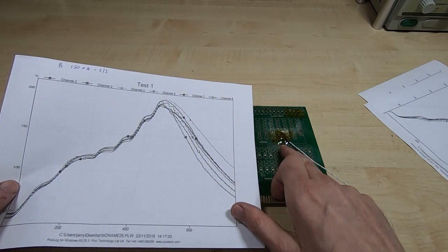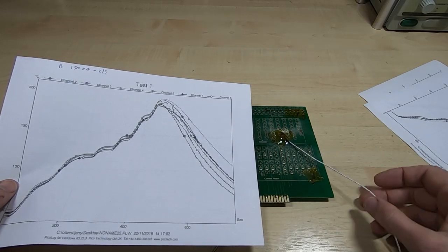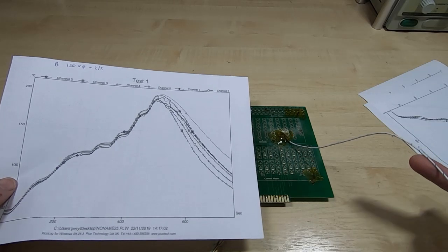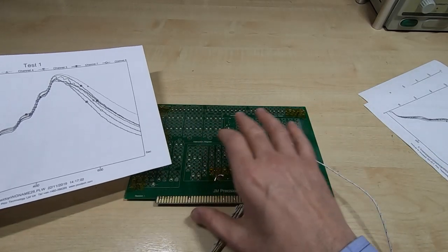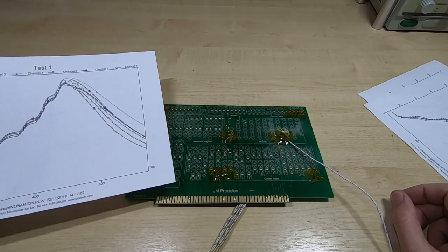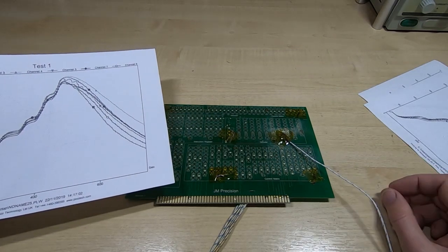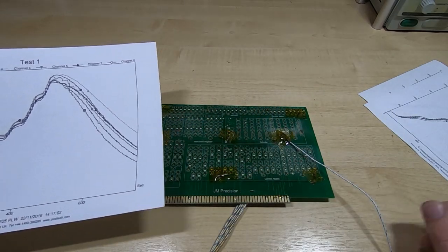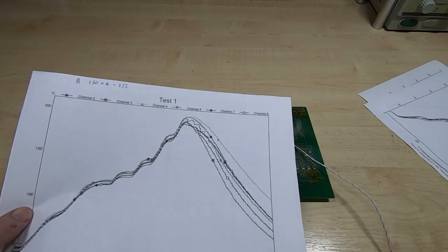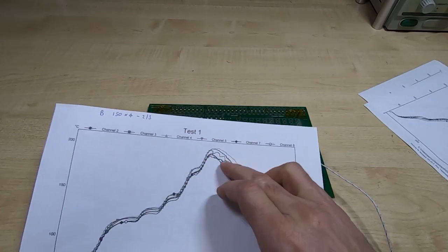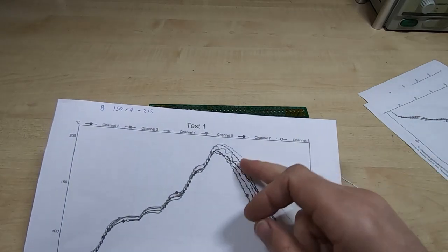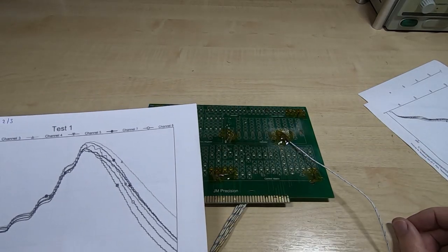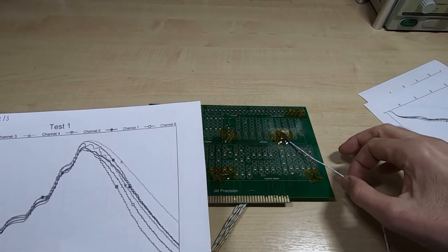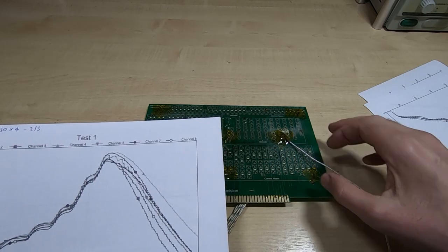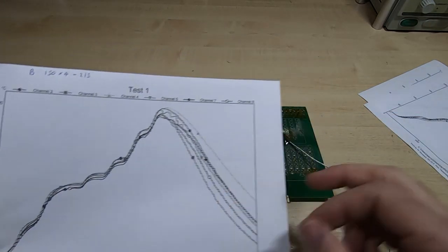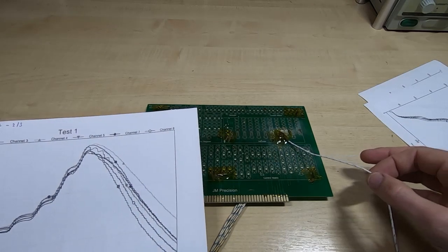I don't then include the probe on the board because it's modified by having this attached to it. But because I can calibrate this very easily every few runs, it makes sure that I'm not being fooled by the probes drifting without me noticing. So that's why there's an extra probe, and I move this around the board for different runs just to check each of the probes I'm using. So you may notice on some of the runs that not all the probes are showing, but it's usually just one that's been omitted because I don't want the results skewed by having this. It doesn't matter if the results aren't the same as the rest of the run because it's not been included in the results, but also I'm comparing it against this probe, not against the others.